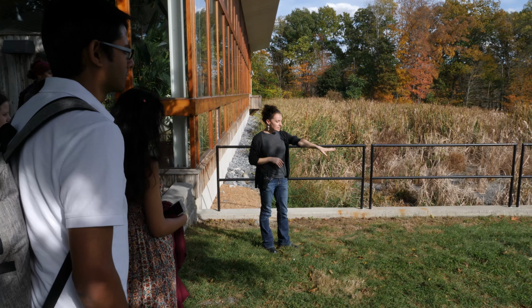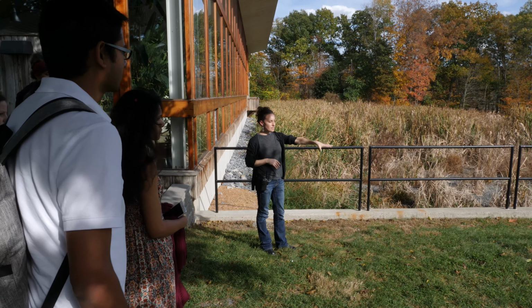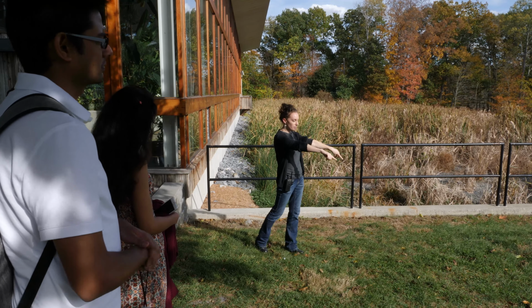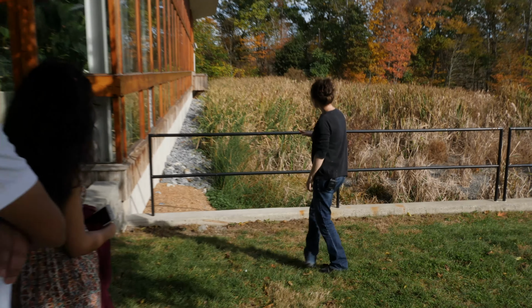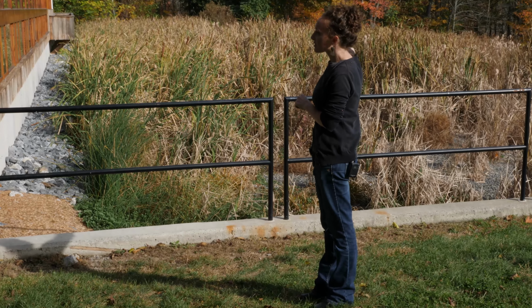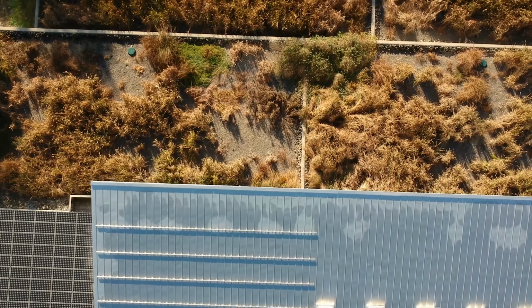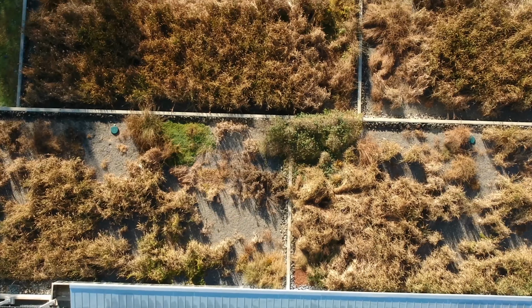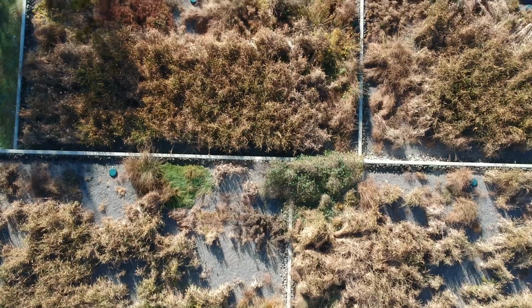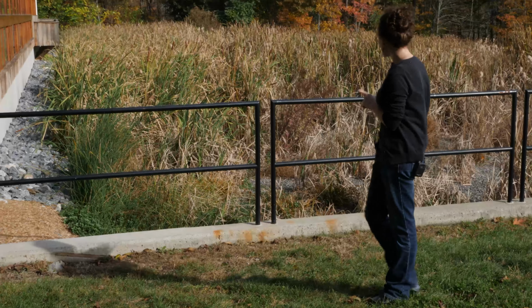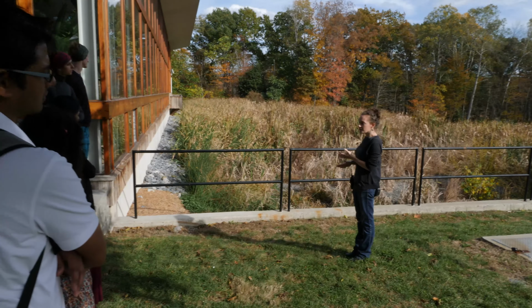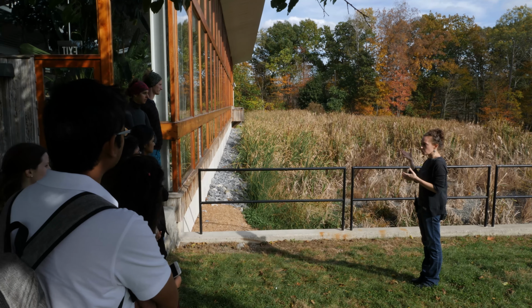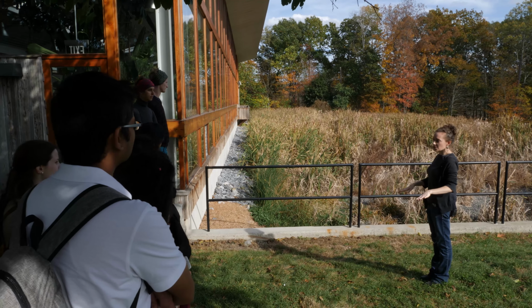There's a splitter box here, so all of the water that comes through is split in half, so part of it flows each way. There's actually 2 different constructed wetland cells out here. Half of the water comes out across the front of the building and flows under this gravel into the first cell, and half of it goes down to the other end and does the same thing. Right in this area, this is about 4.5 feet deep, and it's basically a large swimming pool with a rubber liner. At this point the water is not going into the ground.